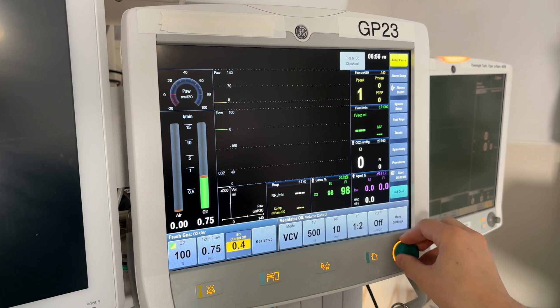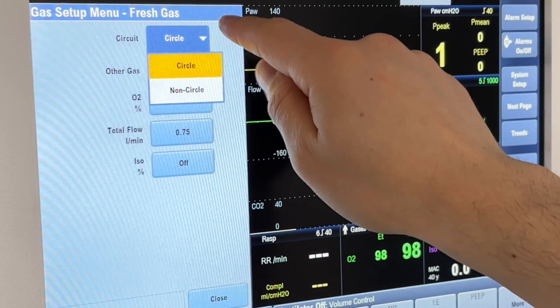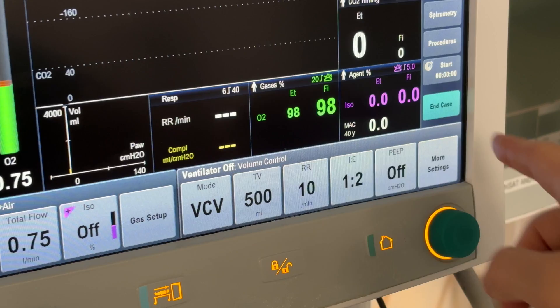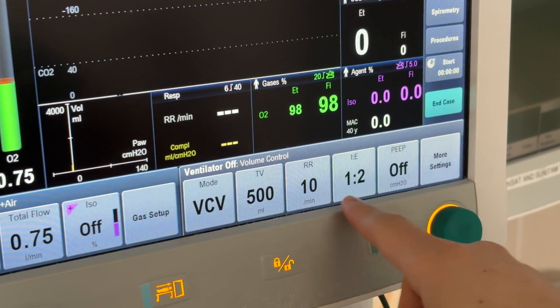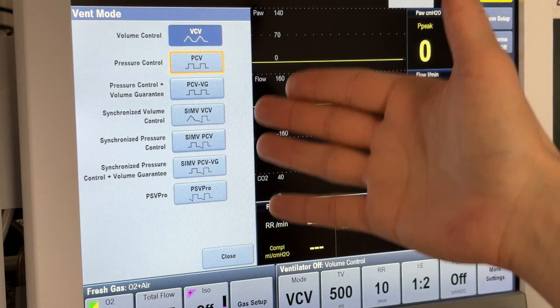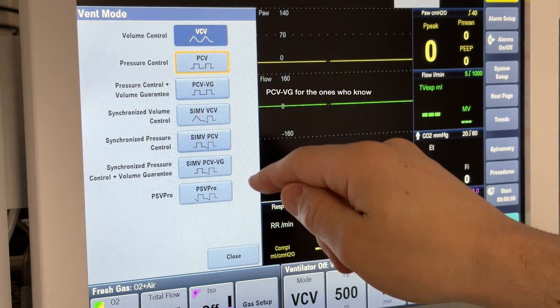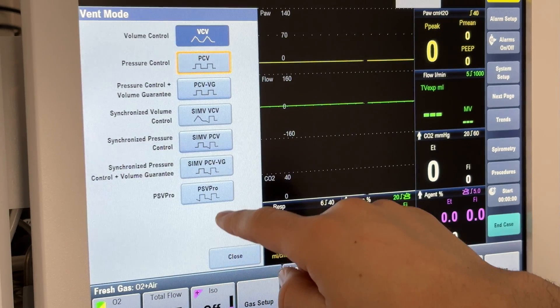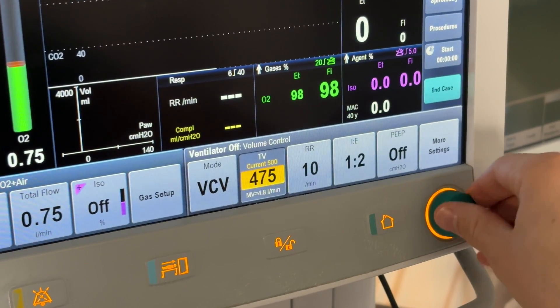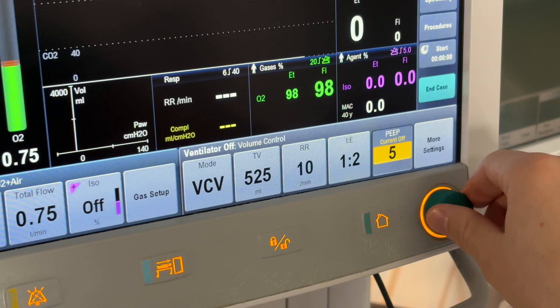You can also dial in the amount of volatile anesthetic that you would like the patient to receive, which can also be controlled with the scroll wheel — we'll leave that off so I don't accidentally anesthetize myself. There are additional parameters such as details about the circuit and whether we'd like to include nitrous oxide, as well as more information about the flows. On the bottom right corner we've got the actual ventilator controls, starting with the ventilator mode. Most ventilator modes are based either on volume control or pressure control, some combination or riff off of them. There's also a pressure support ventilation mode. The rest of these controls are for dialing in specific parameters such as tidal volumes, respiratory rate, inspiration-to-expiration ratio, and positive end-expiratory pressure.